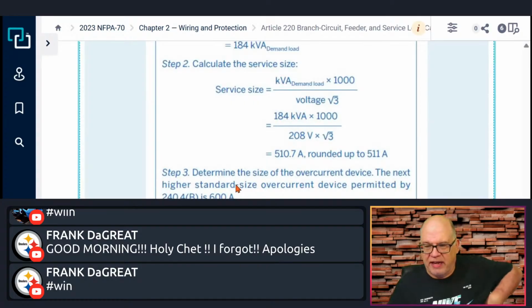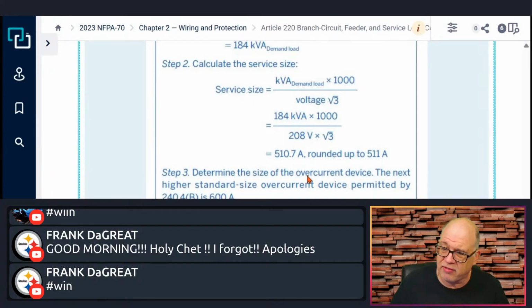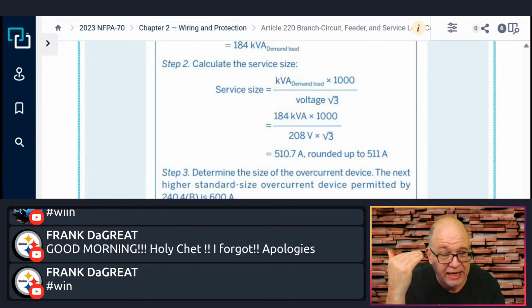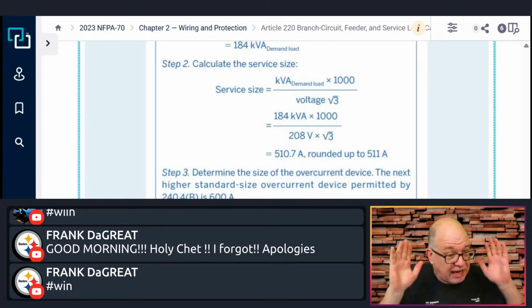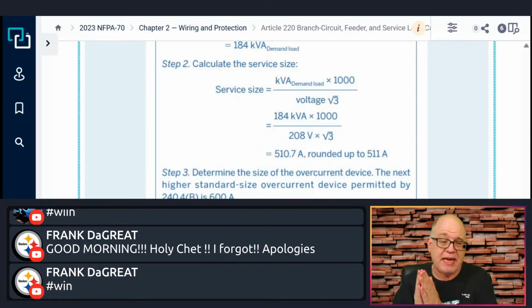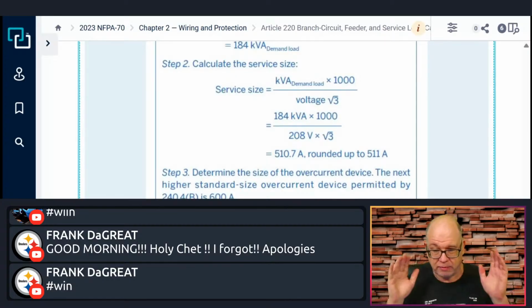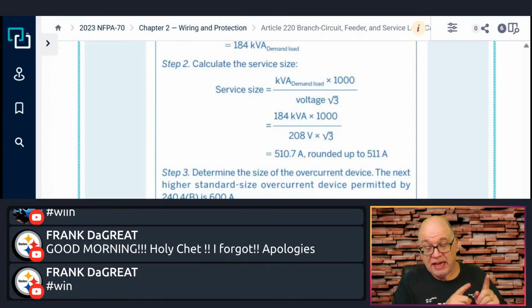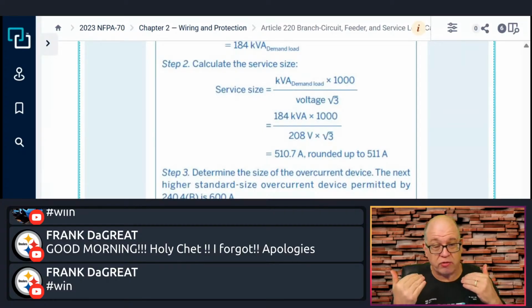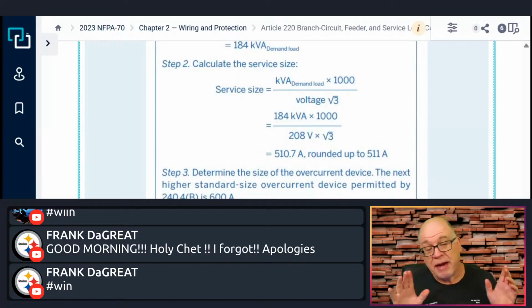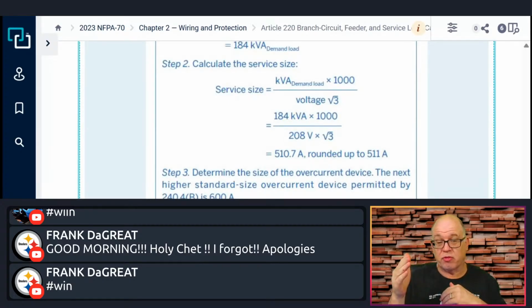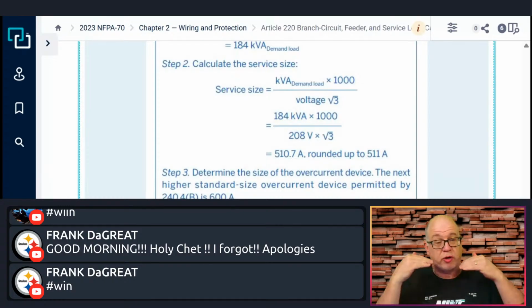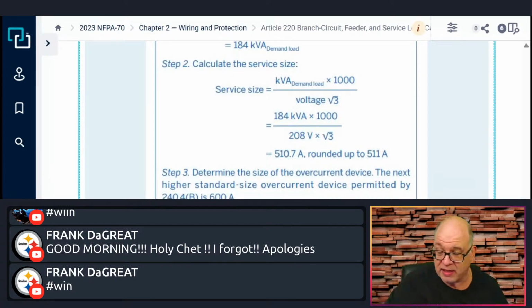So now we go and determine the size of the overcurrent protective device, the next standard size permitted. Why? Because we're not over 800 amps, and we're not supplying branch circuits to receptacles. So we get to use the allowance in 240.4(B), which means we can go up to the next standard size. Remember, our conductors have to be able to carry the load that we calculated, but we can still protect those conductors by going to the next standard size. Now, does anybody know when you can't do the next size up? When it comes to the ampacity, what's the trigger ampacity? When it's over a certain ampacity, we can't use the next size up rule in 240.4(B). Does anybody know?